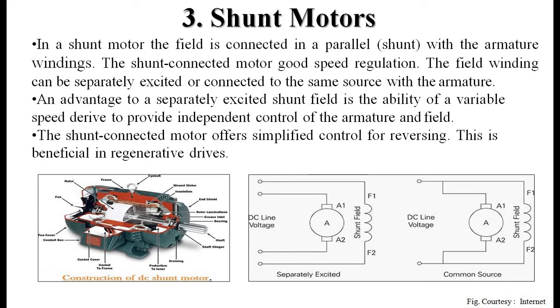The shunt connected motor provides good speed regulation. The field winding can be separately excited or connected to the same source as the armature. An advantage of a separately excited shunt field is the ability to provide independent control of the armature and field. The shunt connected motor also offers simplified control for reversing, making it beneficial in regenerative drives.